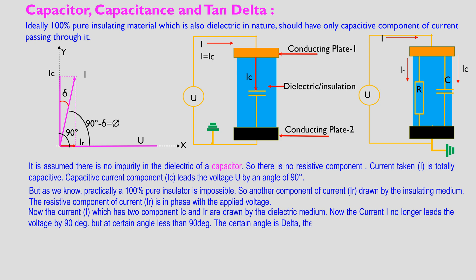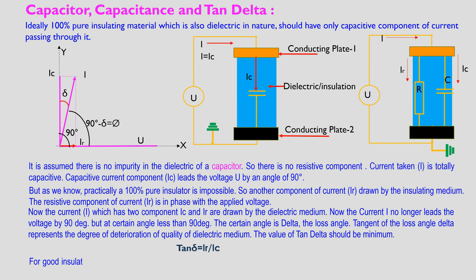This certain angle is delta, the loss angle. Tangent of this loss angle delta represents the degree of deterioration of quality of the dielectric medium. The value of tan delta should be minimum for good insulation. The ratio of Ir by Ic would be quite low. This ratio is commonly known as tan delta. It is also referred to as dissipation factor DF.